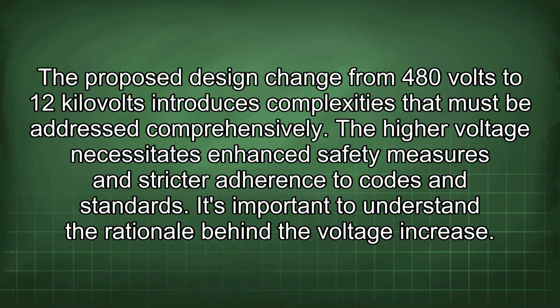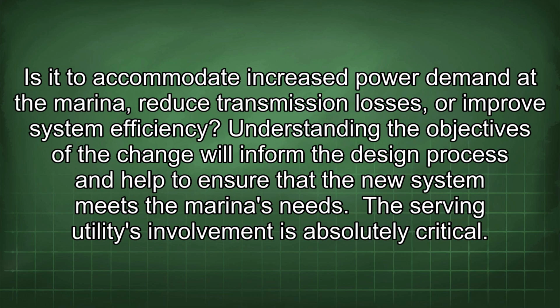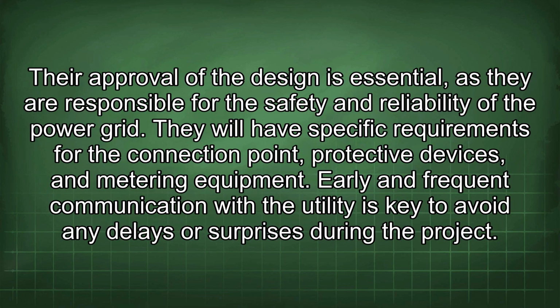It's important to understand the rationale behind the voltage increase. Is it to accommodate increased power demand at the marina, reduce transmission losses, or improve system efficiency? Understanding the objectives of the change will inform the design process and help to ensure that the new system meets the marina's needs. The serving utility's involvement is absolutely critical. Their approval of the design is essential, as they are responsible for the safety and reliability of the power grid. They will have specific requirements for the connection point, protective devices, and metering equipment. Early and frequent communication with the utility is key to avoid any delays or surprises during the project.